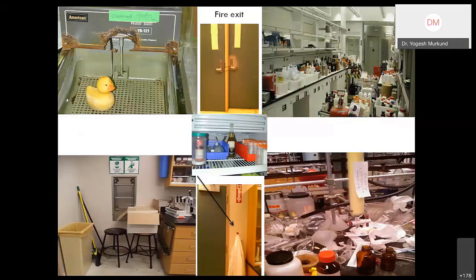This is one kind of eye-opener slide, showing how your facilities or labs should not be, right? You can see that there is a label that it is clean, but you can see a lot of dust and particles and almost corroded area. This will not only cause contamination in your study outcomes, but it is also dangerous for the persons who are working there, right? This type of thing can certainly cause accidents or dangers.